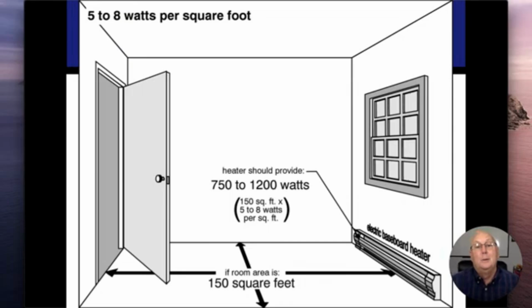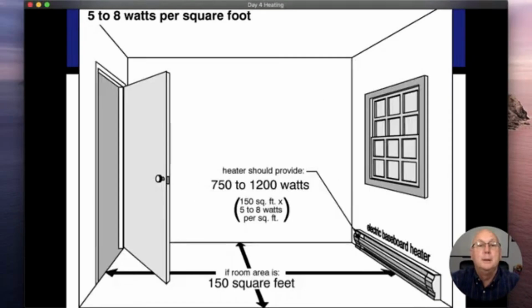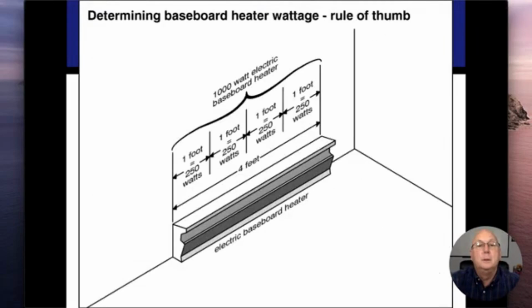All right. So we want to have 7, which is kind of an easy number to remember. 7 watts per square foot when we come in there. So if I've got a 150-foot room, multiply that by 7, and that's going to tell me how many watts I'm going to need for this room. The other thing is going to be a general rule of thumb. Let me skip over a little bit. This again is just a general rule of thumb. We're going to say it's 250 watts for every linear foot, but whatever the data plate says first.